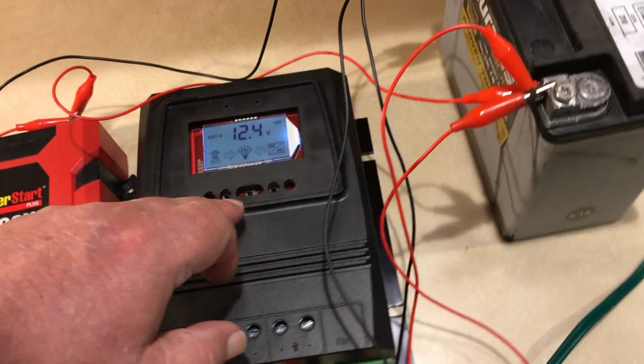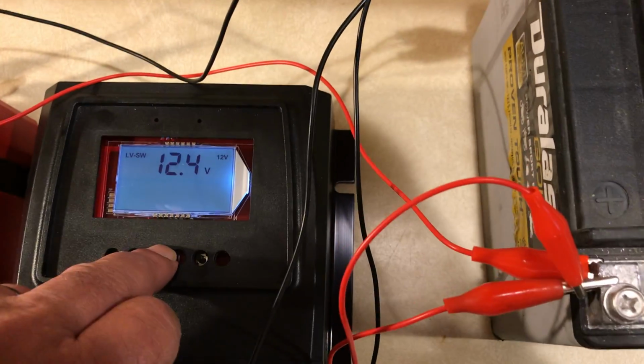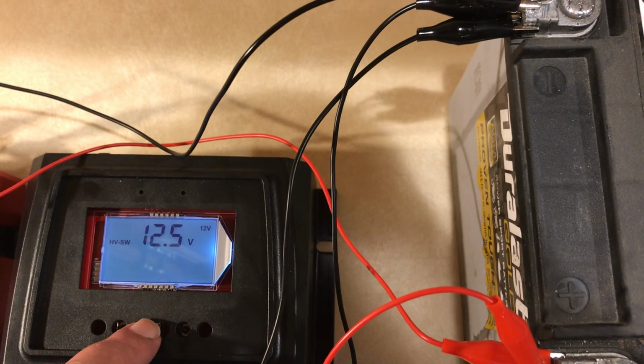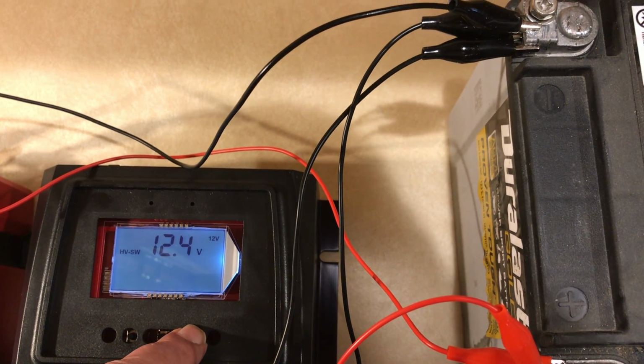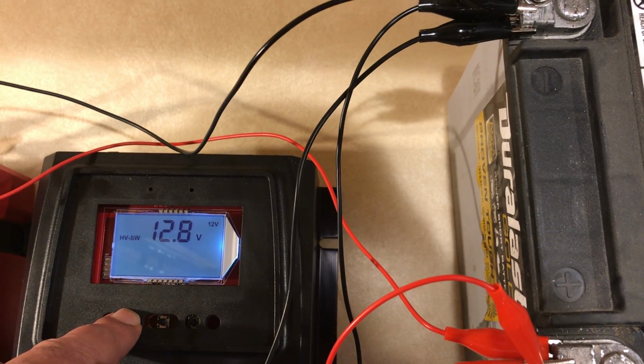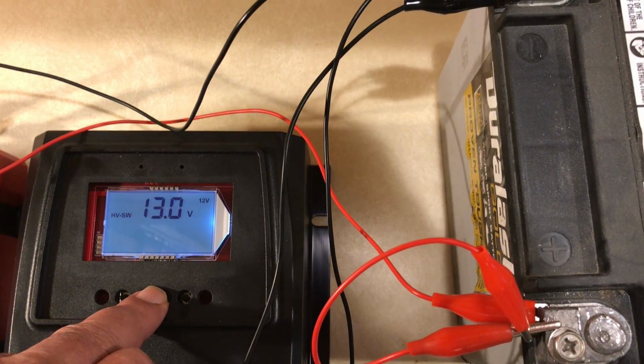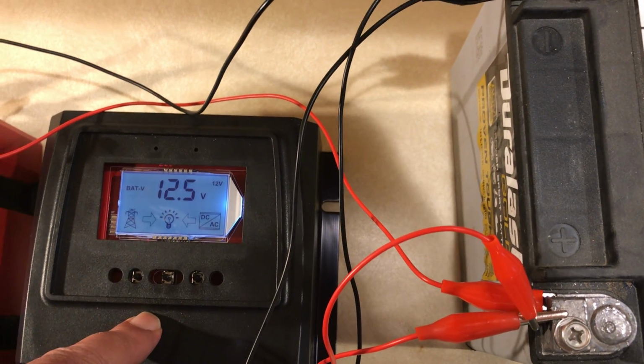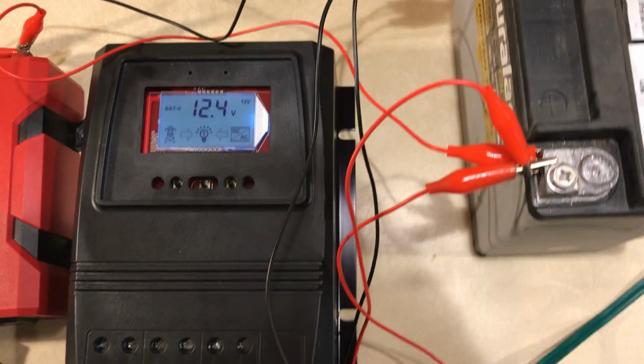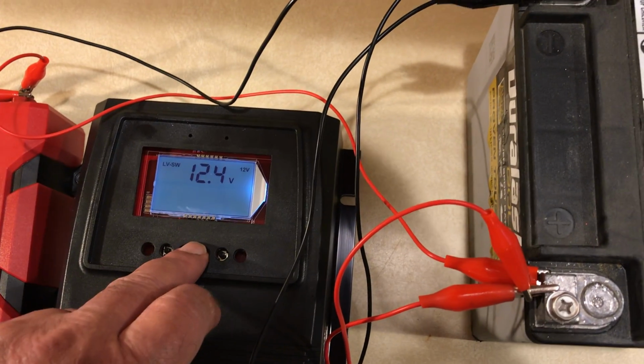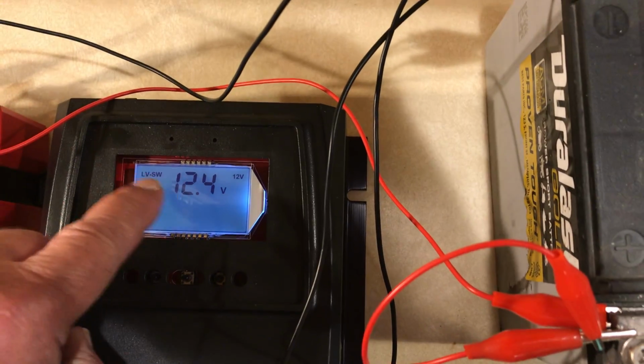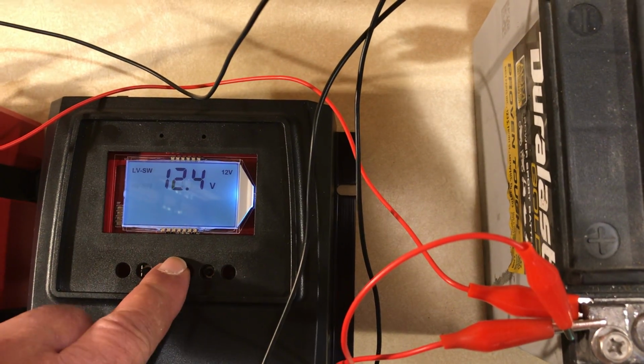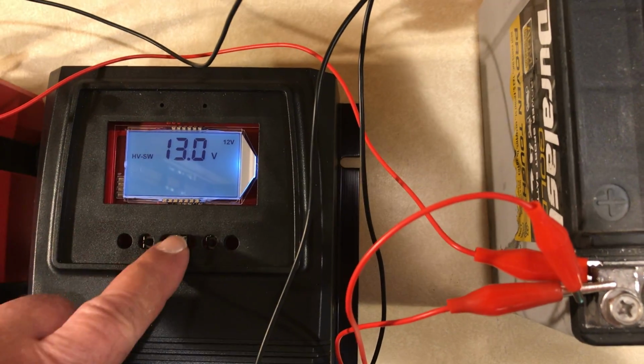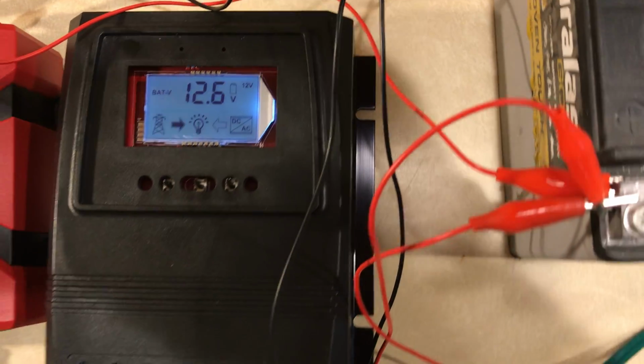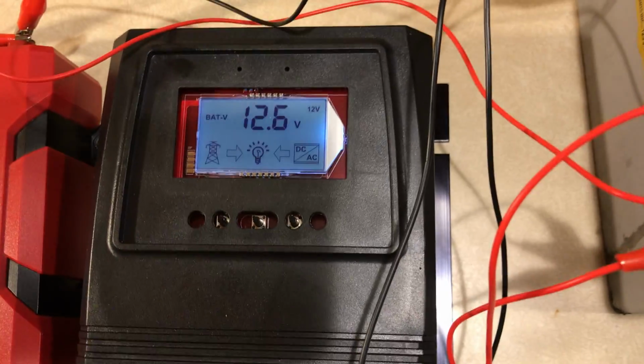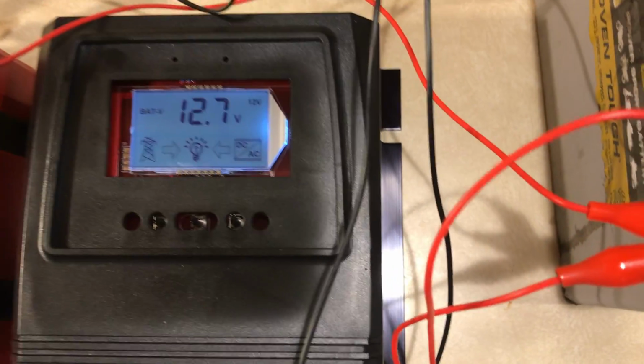Now I'm going to set my high voltage, and I'm going to set my high voltage for 13. I'll push and hold that center button. Now I've got the voltage range for low voltage at 12.4, and high voltage at 13. So now it's going to go to 13 volts before it switches back over.